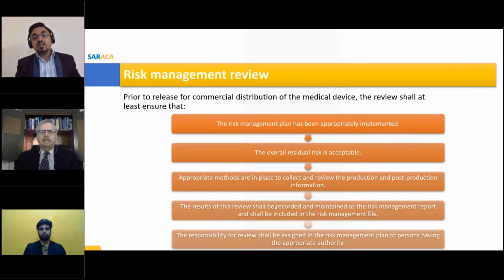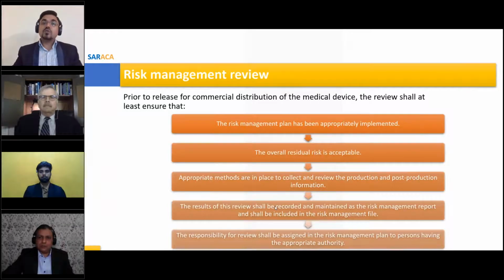I already told you that once the overall residual risk is acceptable, you need to check that methods are in place so that you can collect and review the production and post-production information. Once those methods are there and you have collected and reviewed that information, you need to check the results. The results from the review need to be documented and maintained, and those results form your risk management report, that is the RMR. From these results only can you prepare the RMR, and all these results and this RMR need to be documented in the RMF, the risk management file.